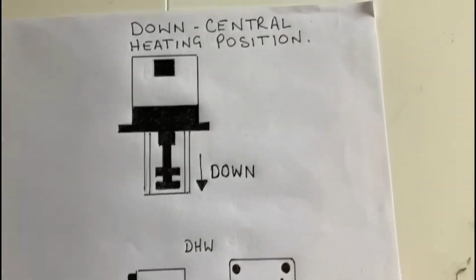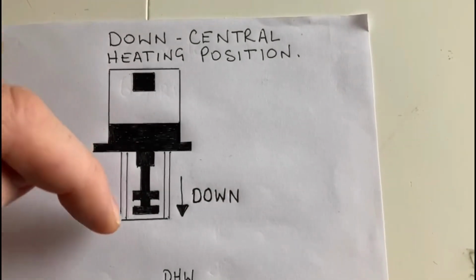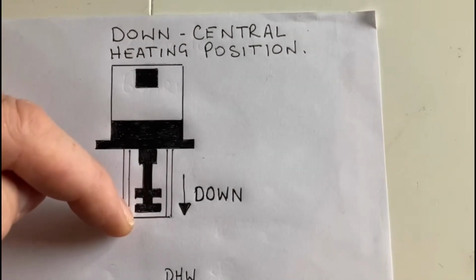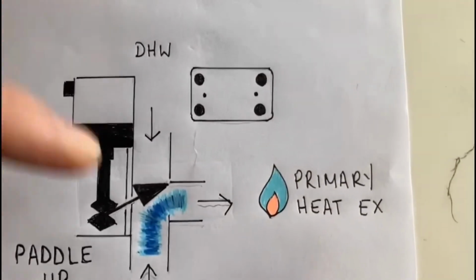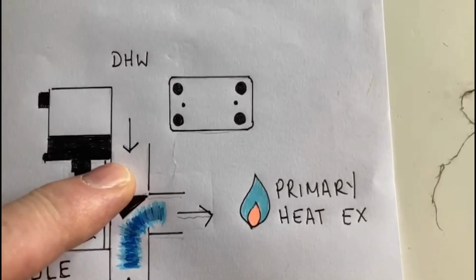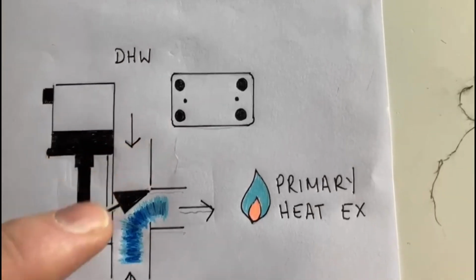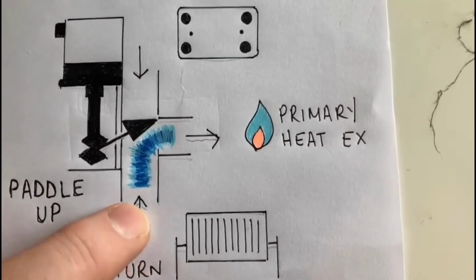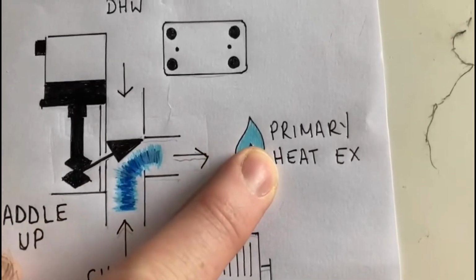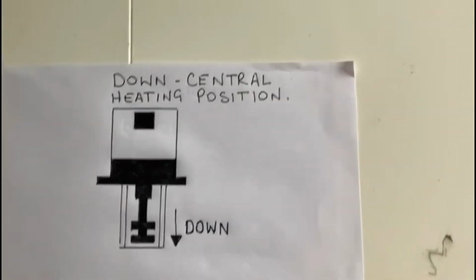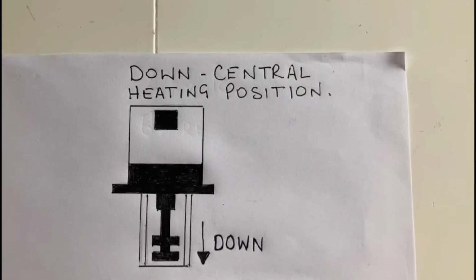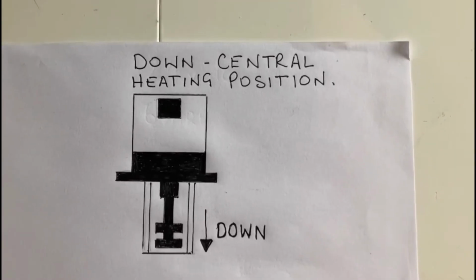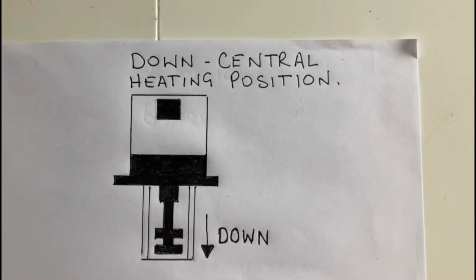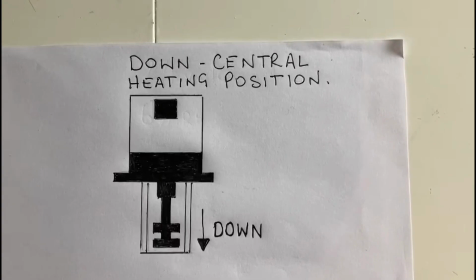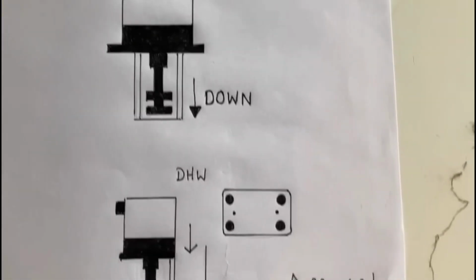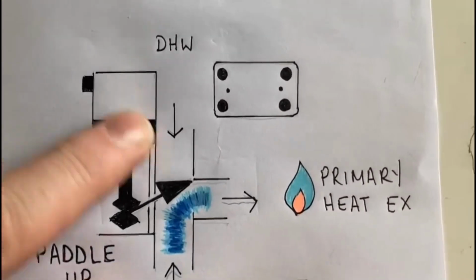And then oppositely, once it's driving down, it's lifting the paddle up, which is blocking off the hot water port and giving a circuit to the central heat and return back to the main heat exchanger. So if you're looking at it, you can see what position the motor and paddle's in, what the diverter valve is in - if it's down, it's in central heating mode because it's blocking off the hot water.